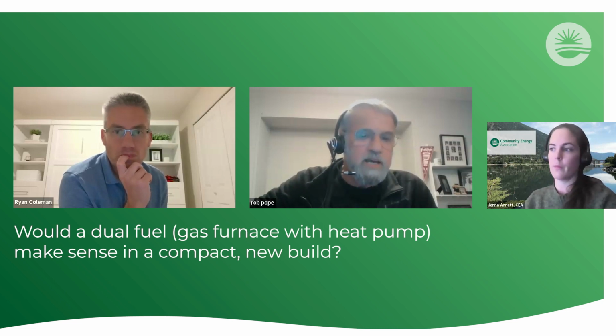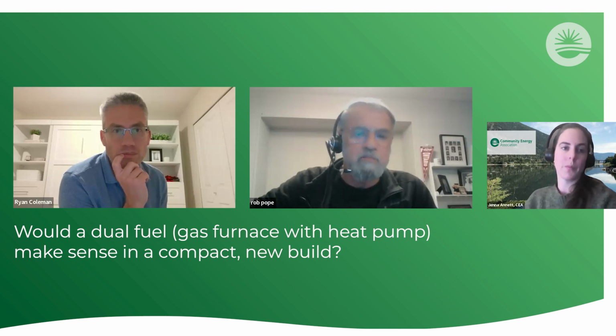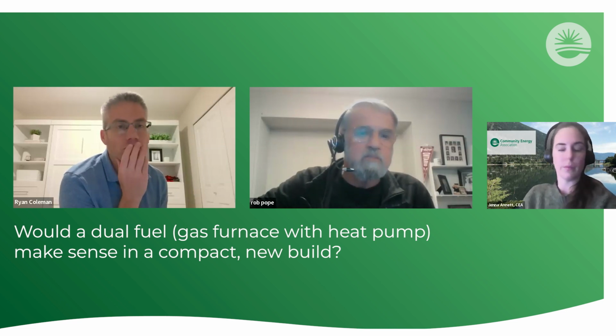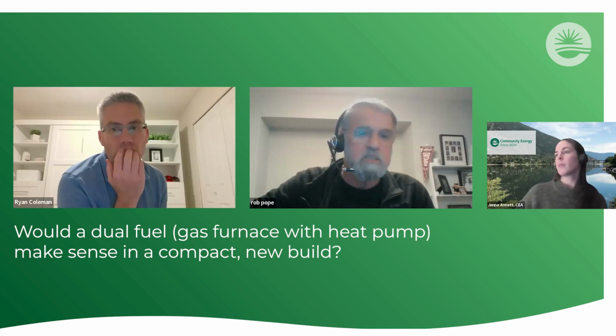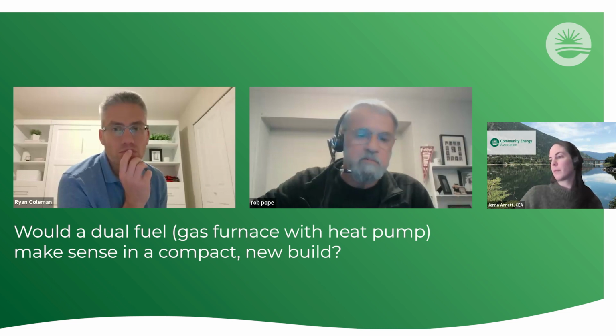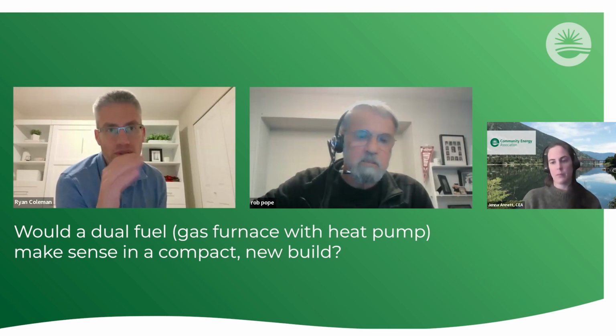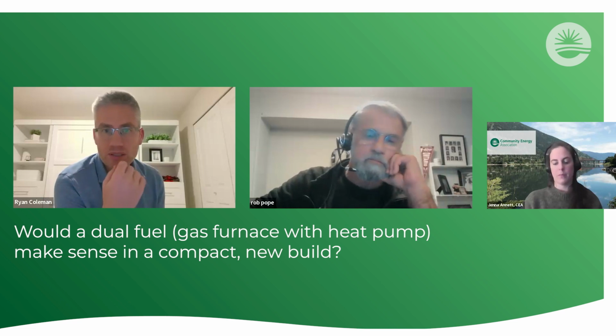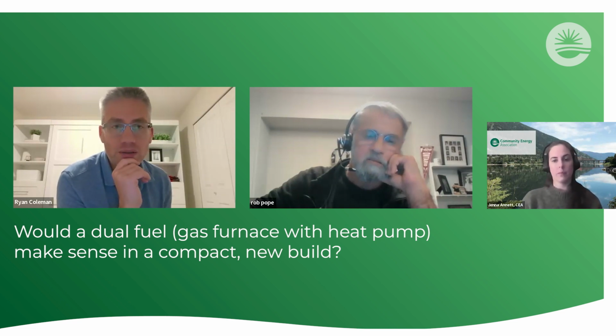If I have to upgrade that panel, that is not a step, it's a leap. It's a huge cost. That would pivot my decision probably to a gas furnace as part of the heat pump package. Yeah, also where they're located and the performance of the house that they're building, because then you could get smaller equipment. And if you're in climate zone 4 or something, you don't even need the supplemental backup. Yeah, you can put in just the heat pump and then you don't have to load up the panel. So yeah, then you're done.